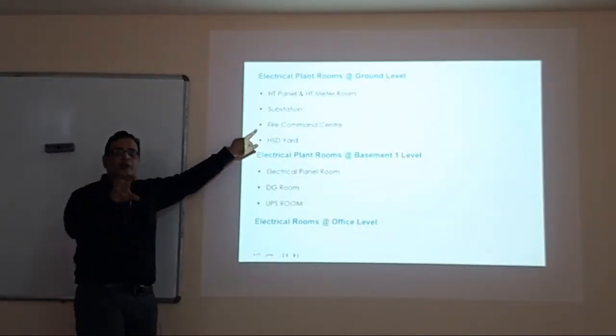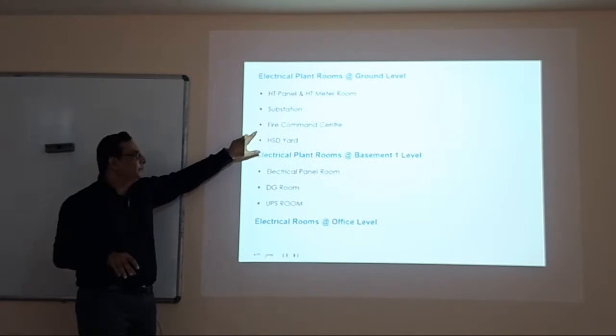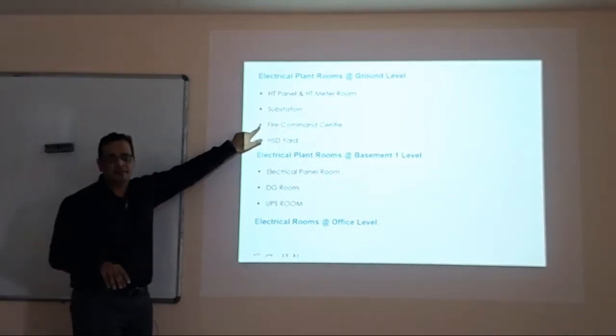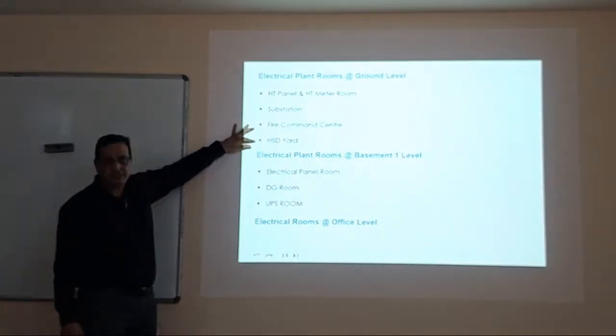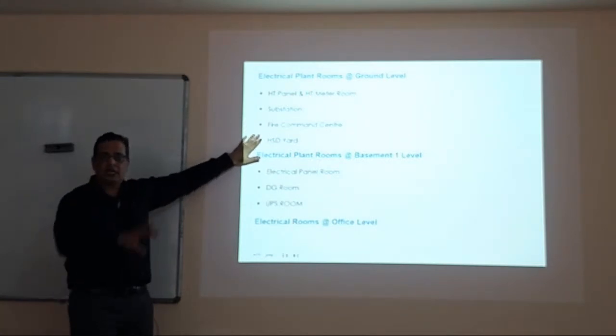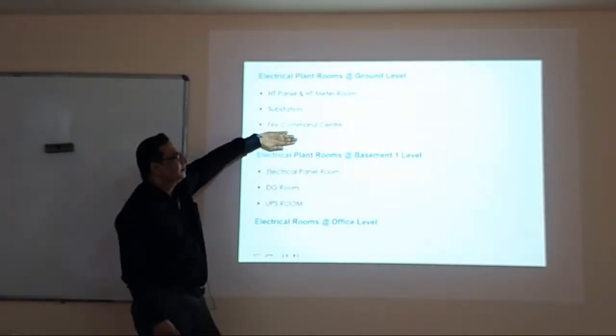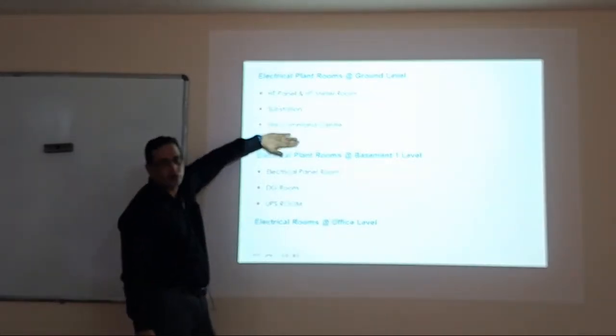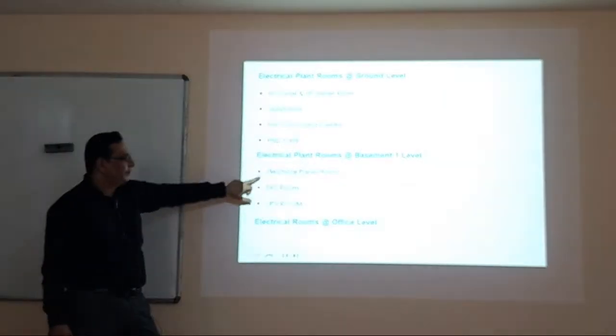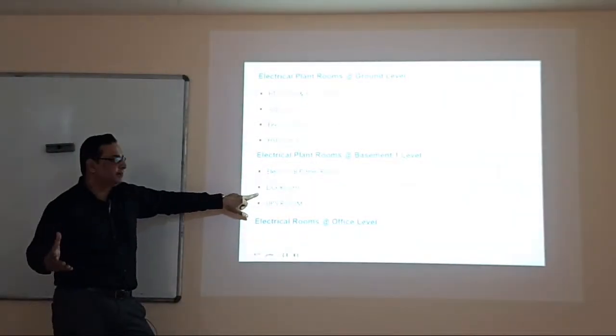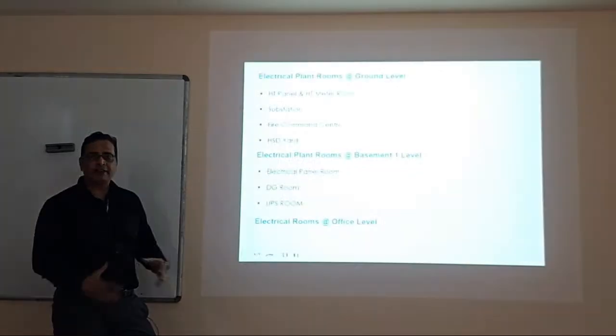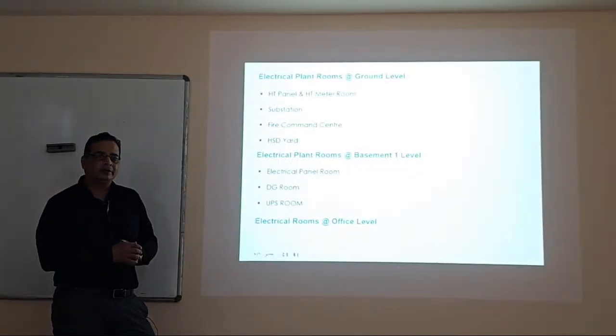It does consume a premium space at the ground floor, but it's a necessity. For a commercial building we also have diesel storage outside, but for a residential building this may not come. Other things will come, but not the diesel storage. Then you have electrical plant rooms, panel rooms, and DG rooms with 100% backup. The UPS basically gives power to all your general and evacuation lighting, and you have electrical rooms at all the office floors.